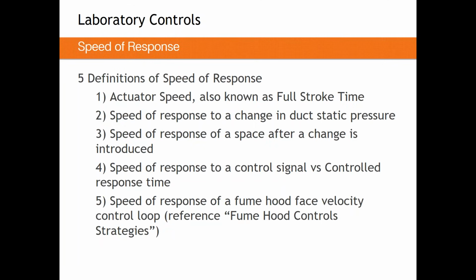If you say, how long will it take to perform a certain action? The actuator speed will tell you generally what the range will be, but that's all it's going to tell you. If you need to make a minor change from 500 CFM to 510, you might get the same total response time out of a standard speed actuator and a high speed actuator. Even though one is moving much quicker than the other, the minute change it needs to make can be accomplished in a single step, essentially.